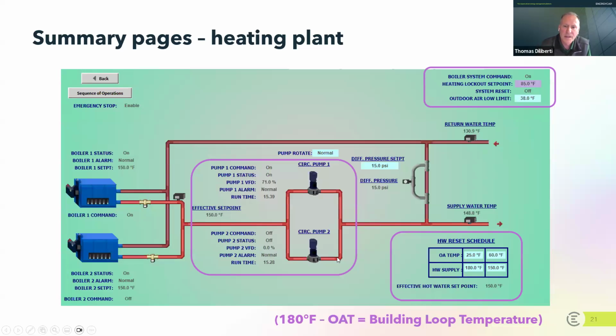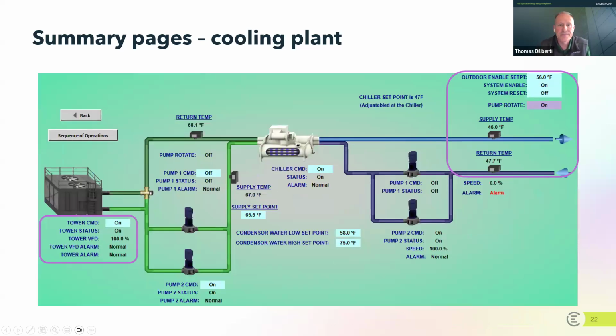Okay, let's see. So we're switching gears on you now, talking about a cooling plant. So moving from boilers to chillers. So here you've got a cooling tower. Some examples of a cooling tower. Again, I have a VFD that's running at 100%. This is a mild day. It seems illogical to me why it's running at 100%. That would be a red flag for me if I'm managing this building. I'd want to go check it out, see what's going on.